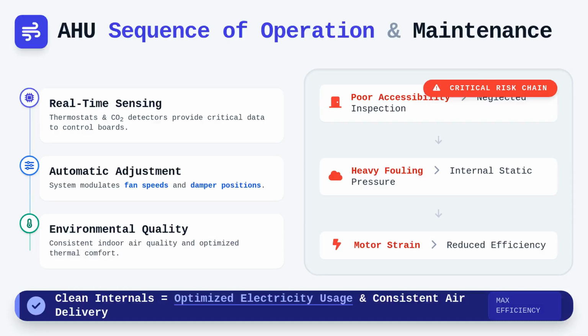The sequence of operation for any given AHU dictates how the unit reacts to environmental sensors, such as thermostats and carbon dioxide detectors, which are strategically placed throughout the air handler framework. These sensors provide the control boards with real-time data, allowing the system to adjust fan speeds and damper positions automatically to maintain indoor environmental quality.